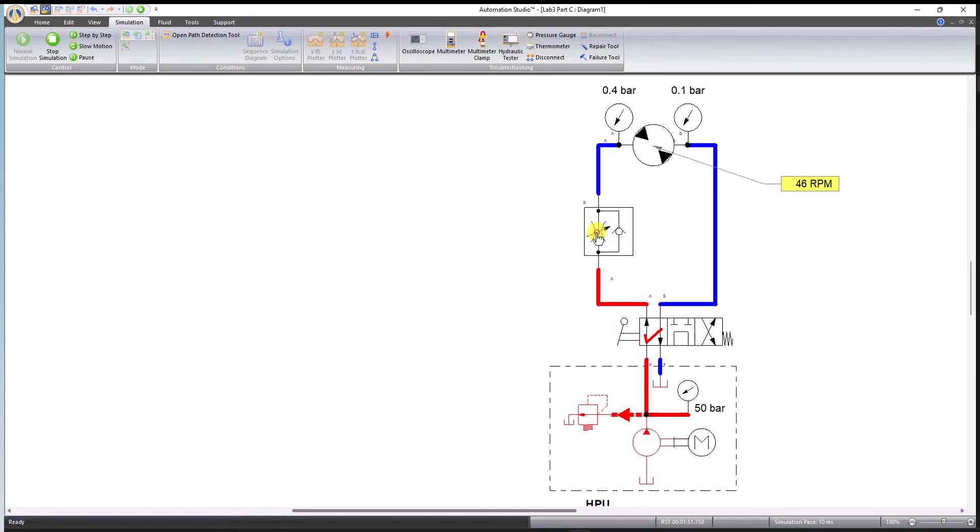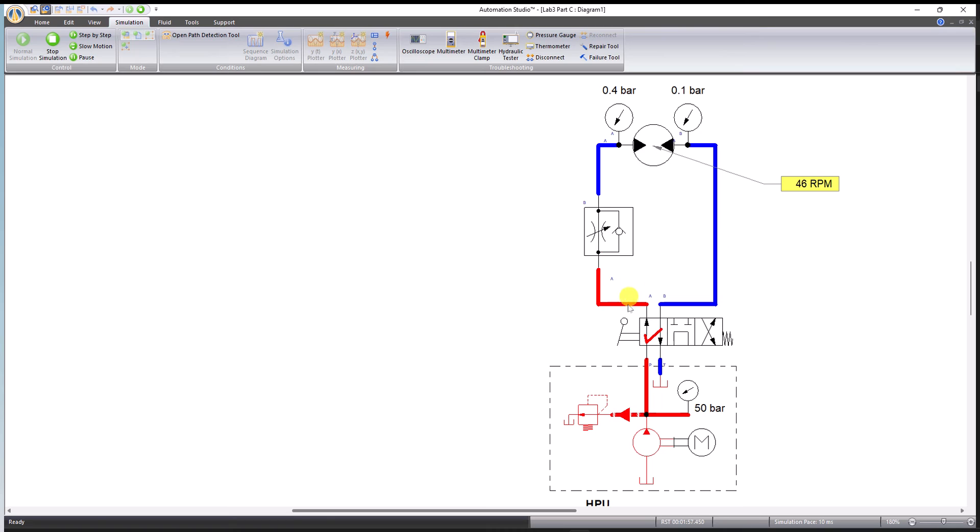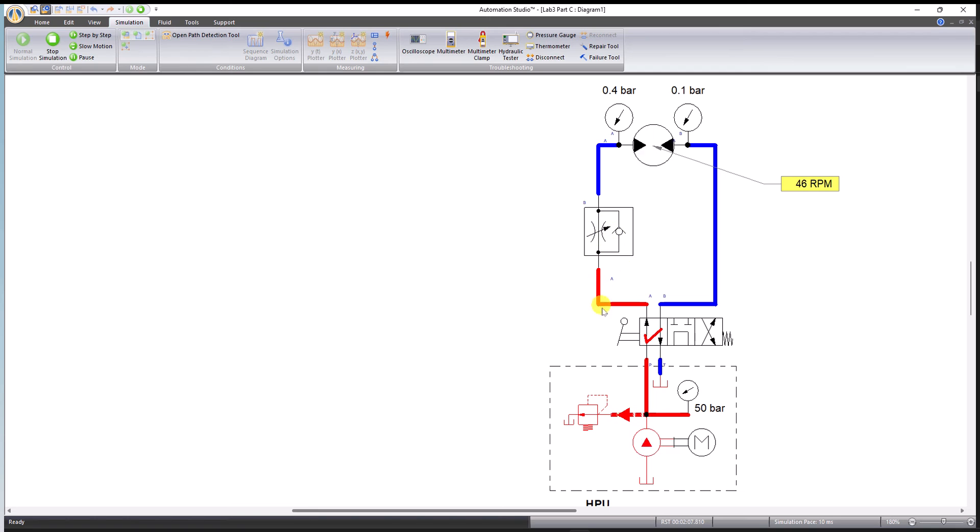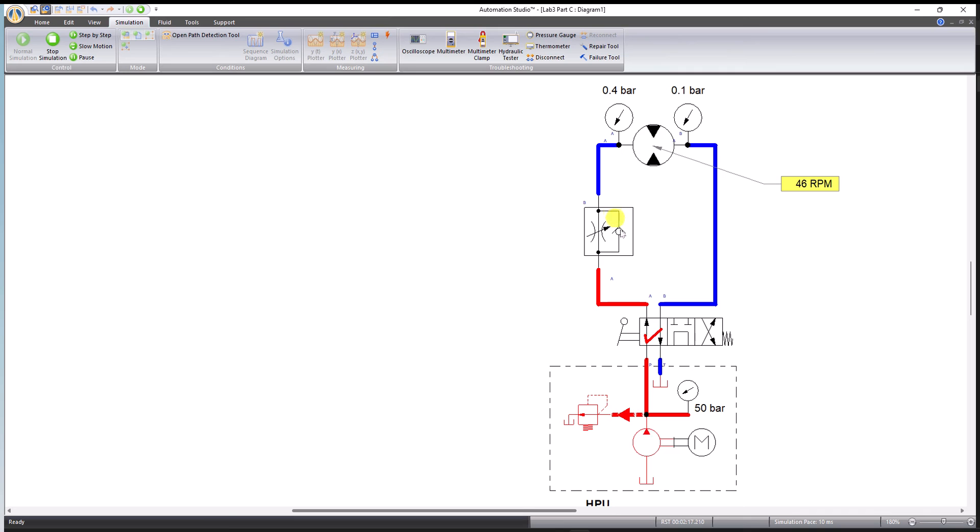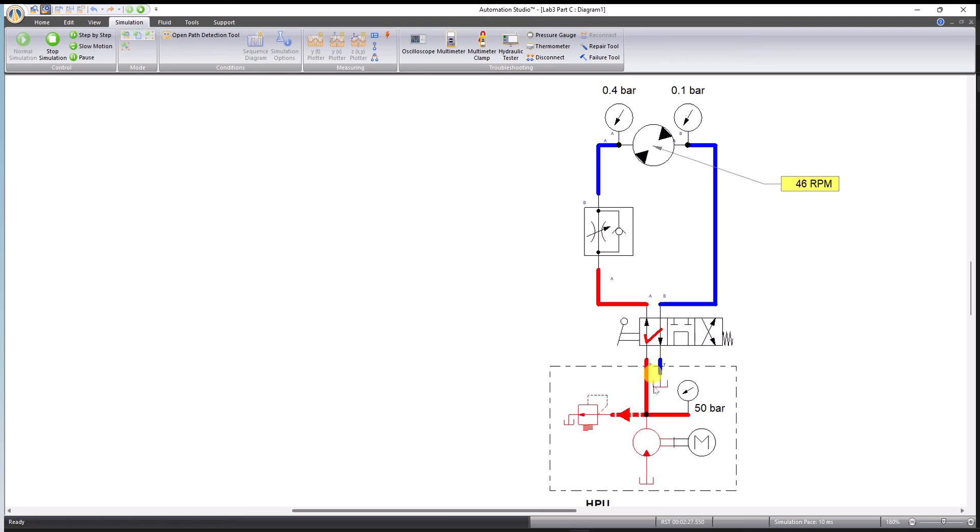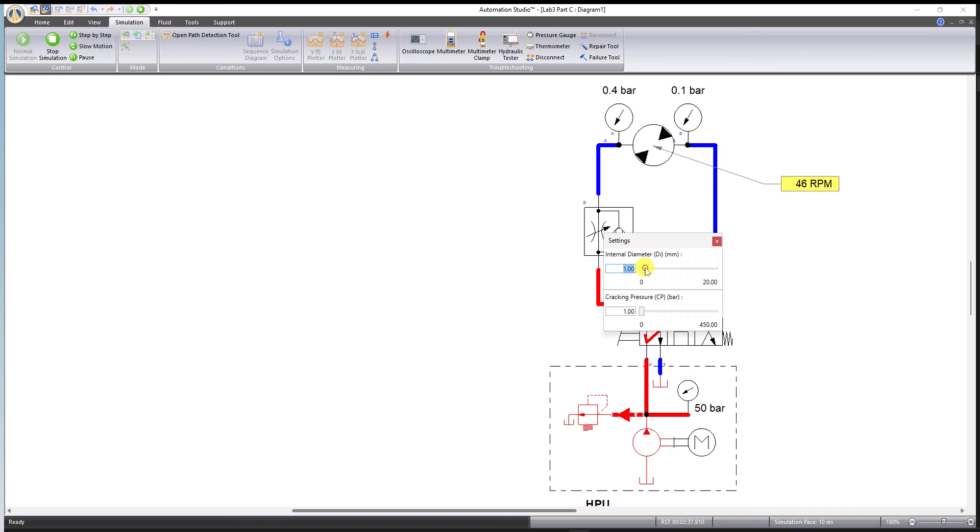But the ongoing flow is only affected by this FCV setup. It should not be affecting the returning flow. When I'm going this way, you see the RPM is reduced drastically from 300 all the way suddenly to below 50 RPM because now the flow is going through this FCV to the left side of the motor. You also notice that the pressure is very high on this line. The flow path for the fluid is very difficult, so fluid is returning to the tank via the pressure reliever. We can increase the diameter so that fluid is encouraged to travel through here.